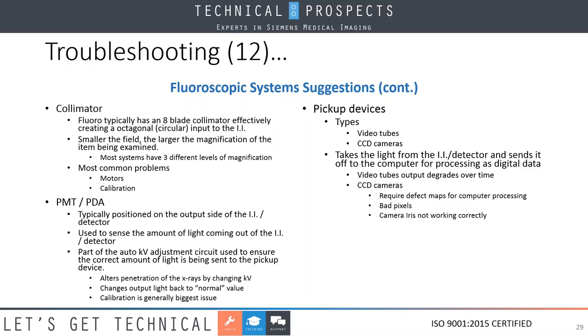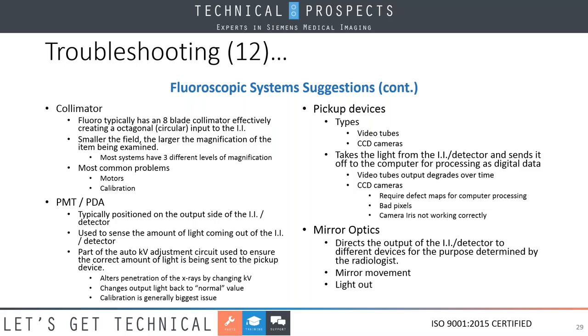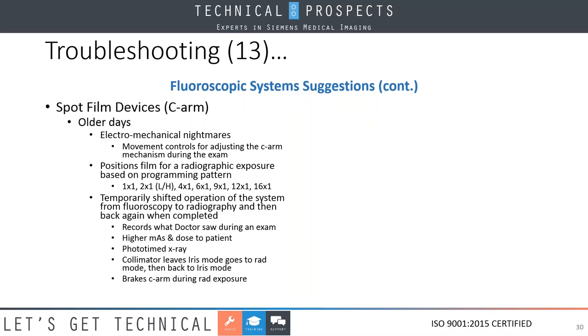All right. Is the camera iris working correctly? This is what's going to control the amount of light getting into our CCD camera. So you've got other factors to look at here, and it's a process of elimination in doing this. The mirror optics, this directs the output to where we want it to go. On some systems no longer use this, other systems have still got it. Does the mirror move in or out? Are we getting light out of the mirror? Again, these are things that you need to be aware of as we go through.